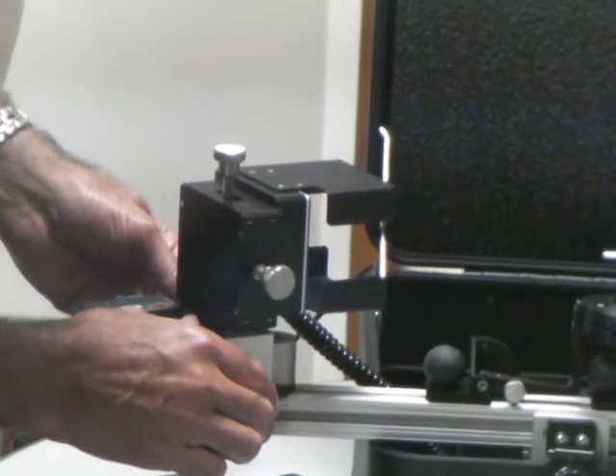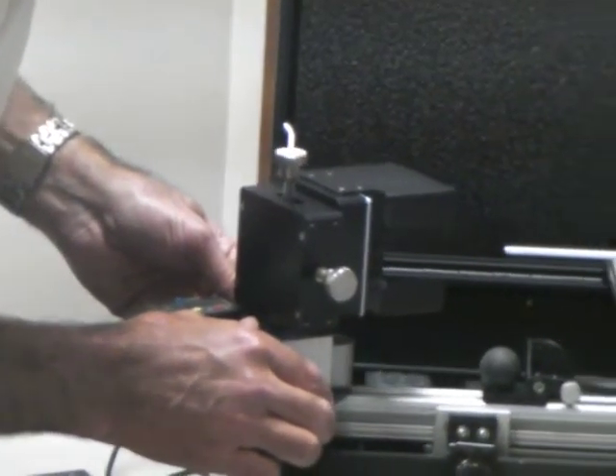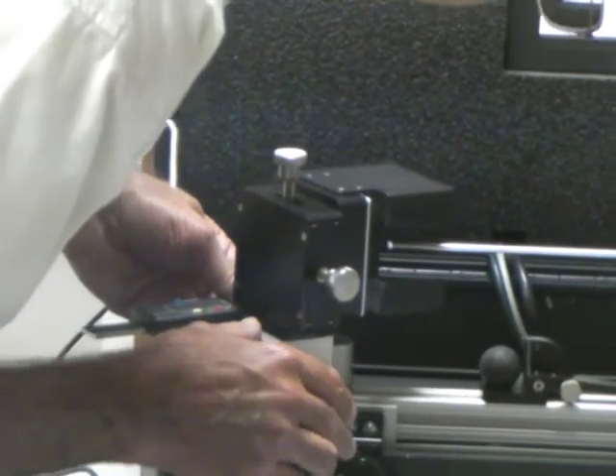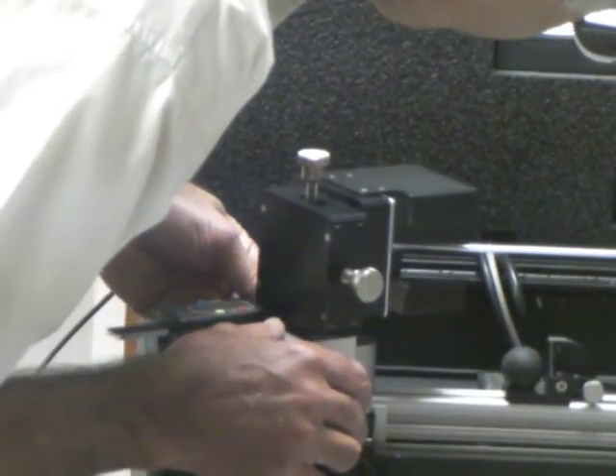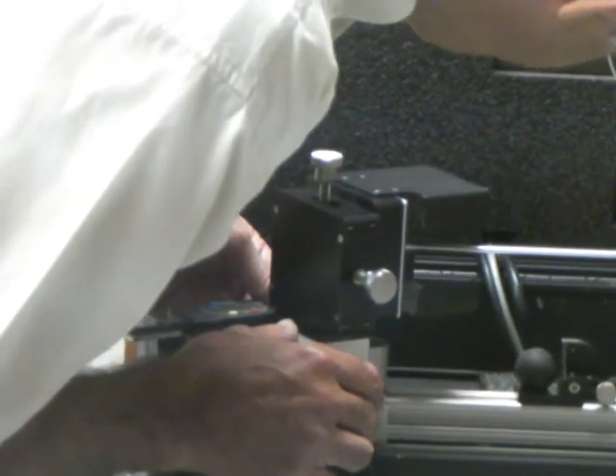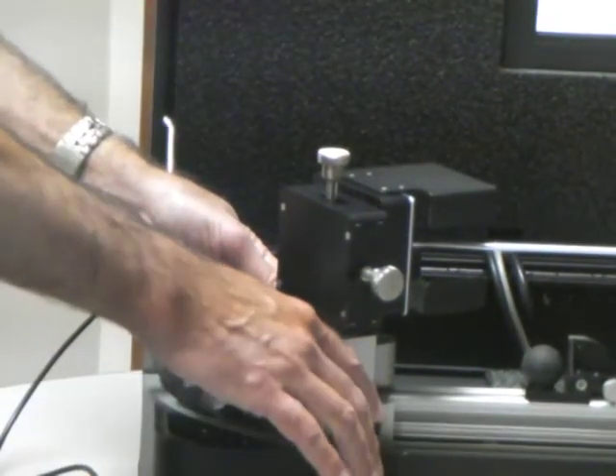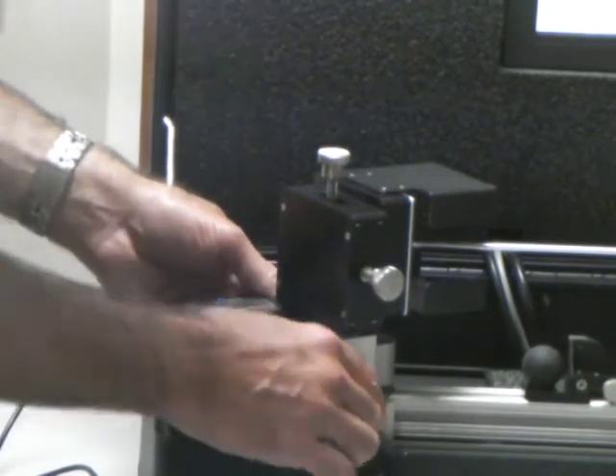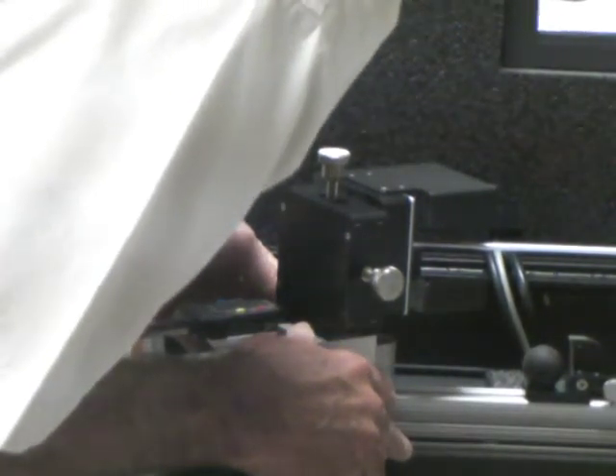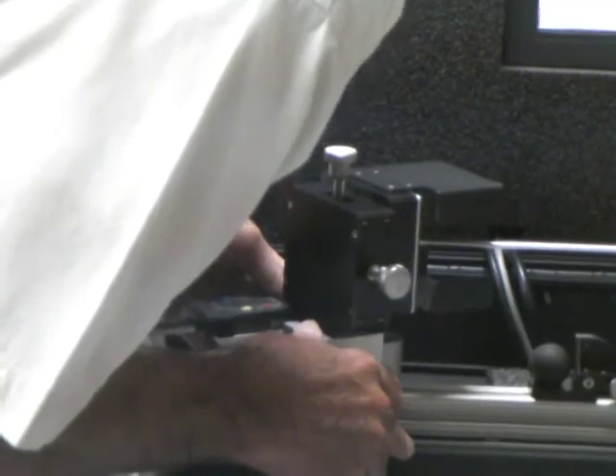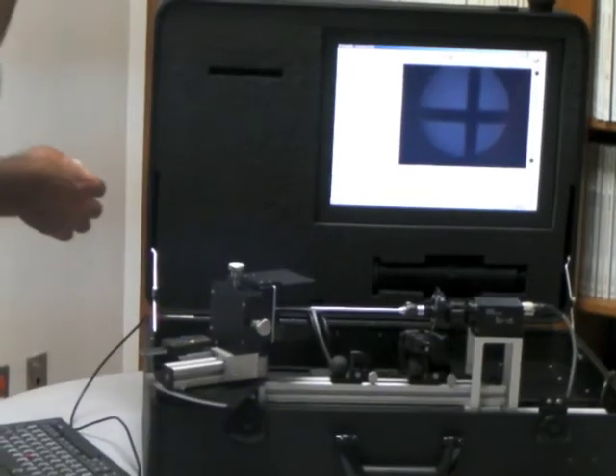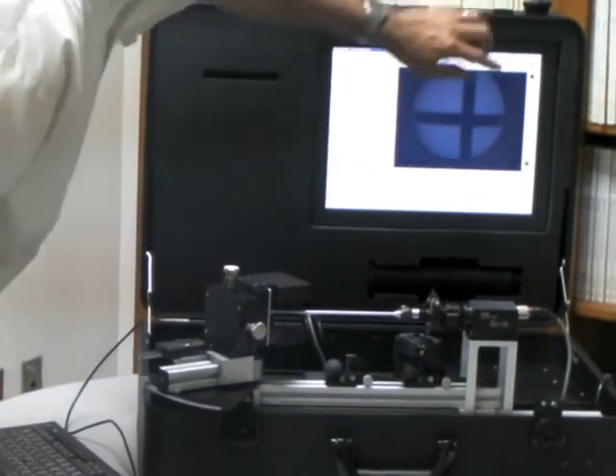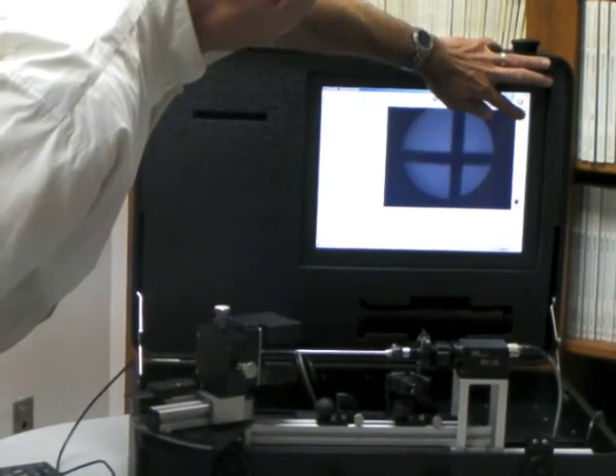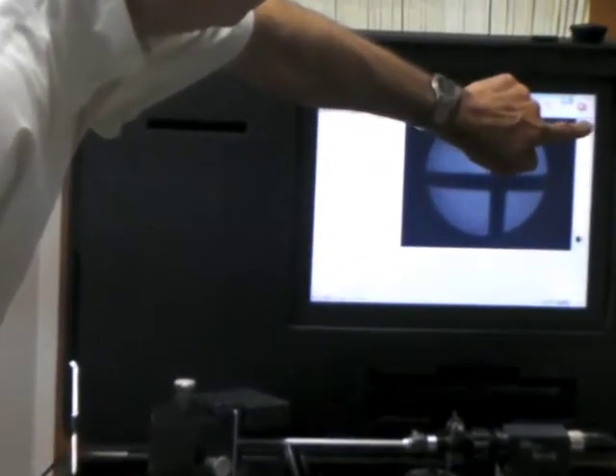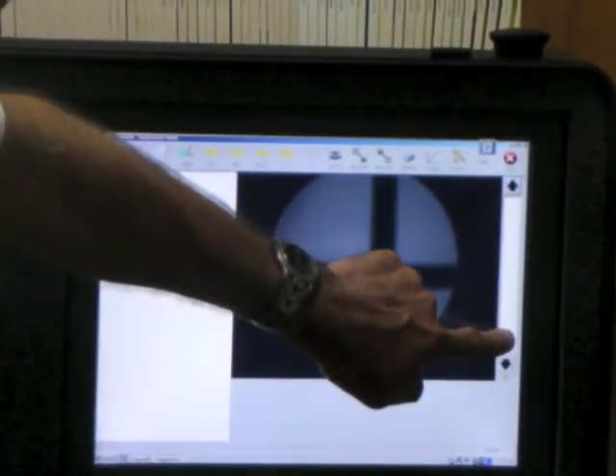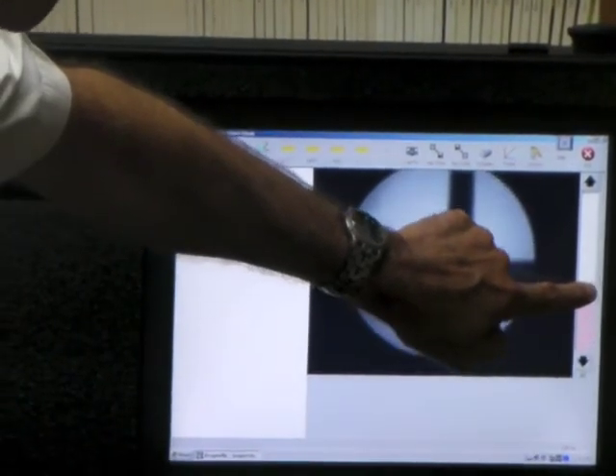The next thing we do is we move the whole rail system such that the tip of the scope is also at the zero. So I can move it slowly and carefully. As you get close, you can actually see the reflection of the tip of the scope, so it's not very difficult at all to put the scope in the proper position. So I'll get it right about there, and it's very close. The next thing to do, I'll increase the light a little bit. We can either increase the light by repeatedly pressing this arrow, or we can slide the slider up and down.